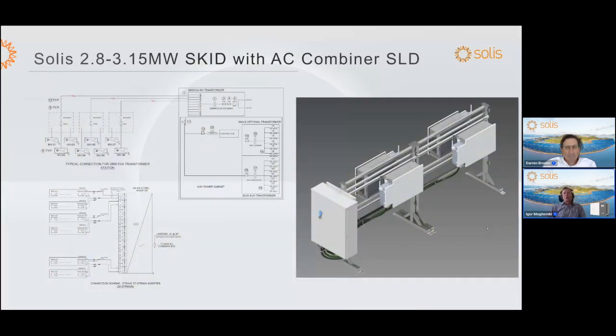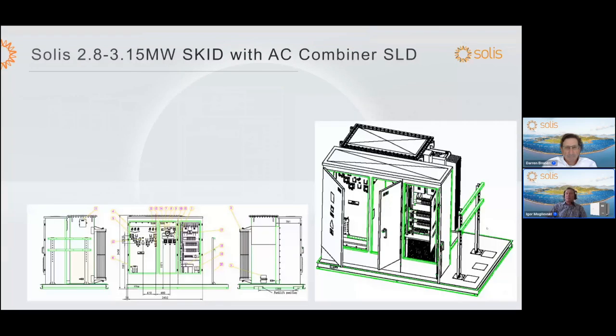We also provide for smaller utility scale projects, especially ones that require different interconnection voltages other than 34.5 kV, a smaller skid, 2.8 to 3.15 megawatt. It's a similar design as the previous skid, where you can connect multiple 350 kilowatt inverters with AC combiner directly into the low voltage cabinet. That skid is 2.8 to 3.15 megawatt. It starts at 12.47 kV up to 34.5 kV. So you could have different medium voltage combinations on this particular skid.